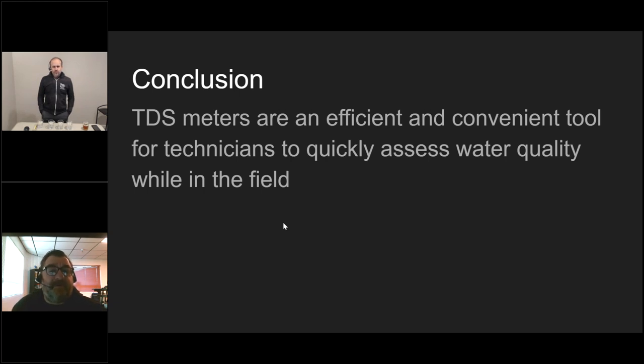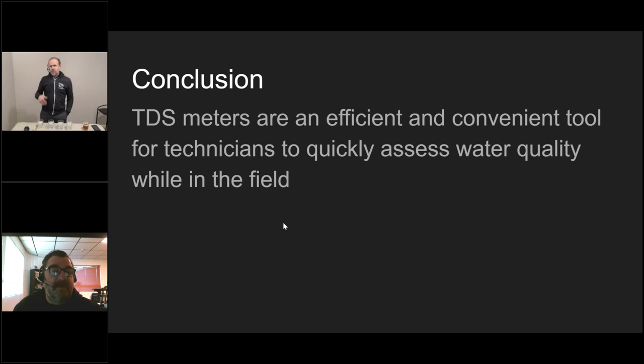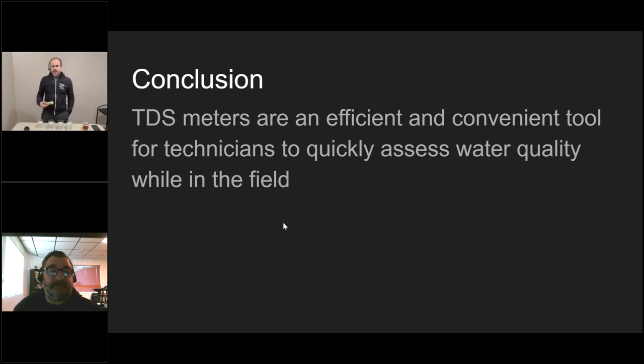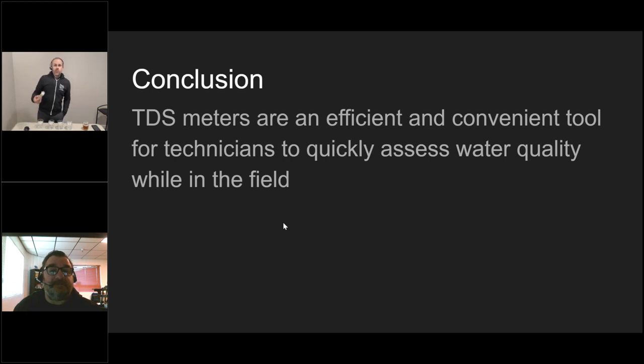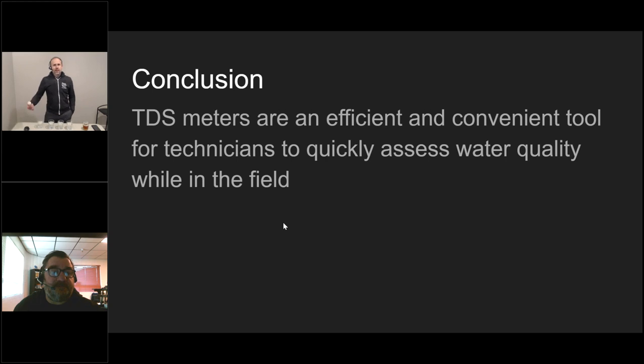Do you have anything you want to close with before we wrap it up? Just to the point that you made earlier about water testing, I would recommend at the very minimum, starting with a TDS meter and at every single service call, somewhere on the form that you use, the app that you use, find a space where you're going to record that total dissolved solid number, usually before and after, and just start there. Start there as an easy place to put it into your routine. You'll find it doesn't take very much time. And then it becomes a habit because you'll want to look back at that information occasionally, especially when you're referencing it for a customer and they want to know maybe why their machine scaled up or why their boiler failed. You can go back and look at that information and you can have a history that kind of tells a story of how did we get to this point. So that's a simple thing that you could start with. And then from there, once you've made it a habit, you can add to that with the other analytes that we've talked about.